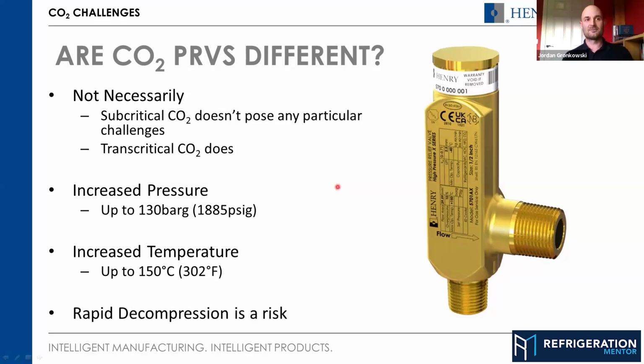And the final point I put on here is rapid decompression, which is a term that is quite well known in the oil and gas industry, where the temperatures are much higher again. For those of you who maybe don't know, it's a phenomenon where, with an elastomer seal like an O-ring, the gas, because of the high pressure, can creep into and impregnate that material. And then when it's exposed to atmospheric or low pressure, the gas bursts out of the material very suddenly and effectively rips it to bits. So in a relief valve, if you're using an elastomer seal in the seat itself and the valve opens, you can see this rapid decompression, which is why choice of material is very important for a CO2 valve, especially transcritical.